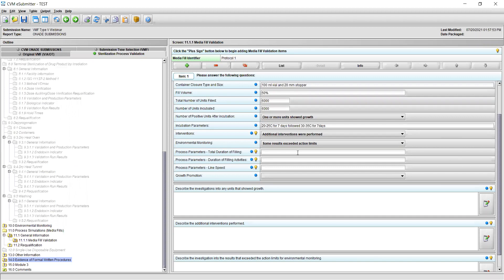Fields 11 through 13 are specific to process parameters of the media fill. In field 11, state the total duration of filling in hours and minutes, for example 12 hours. This time should include all interventions and stoppages. In field 12, state the duration of filling activities in hours and minutes. Provide the total time for which actual filling activities or interventions were performed. This should not include stoppages unless they are a normal part of manufacturing operations, for example a lunch break.